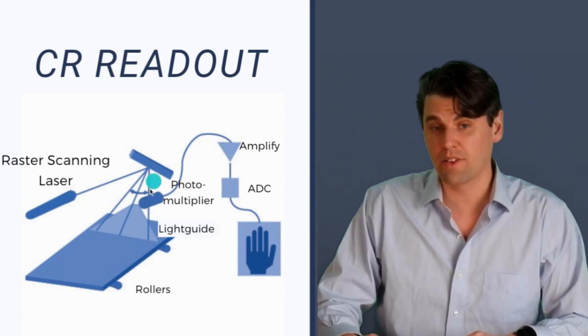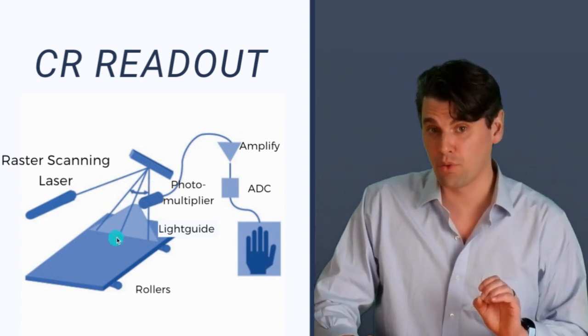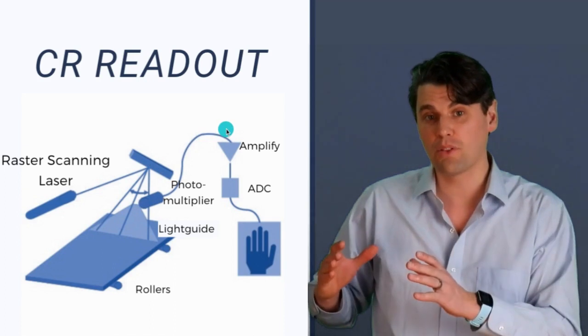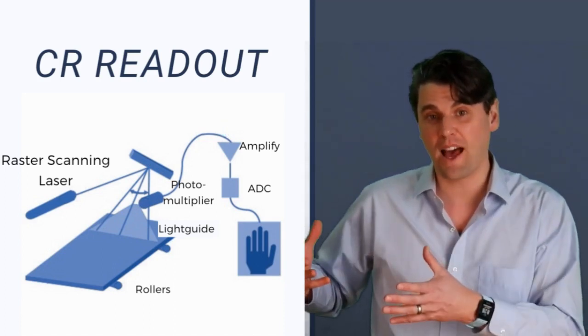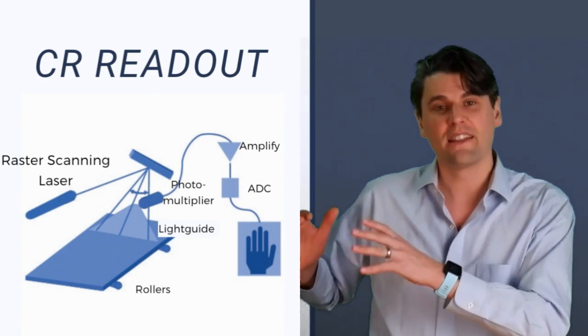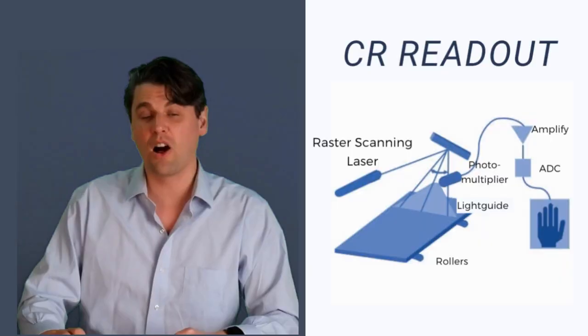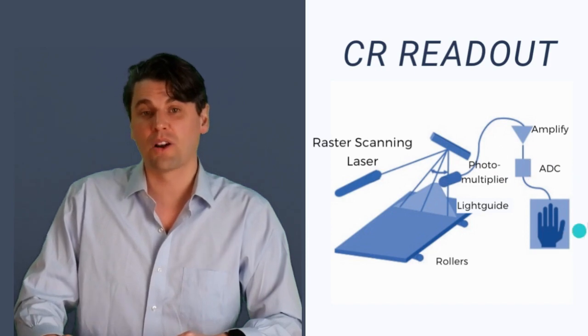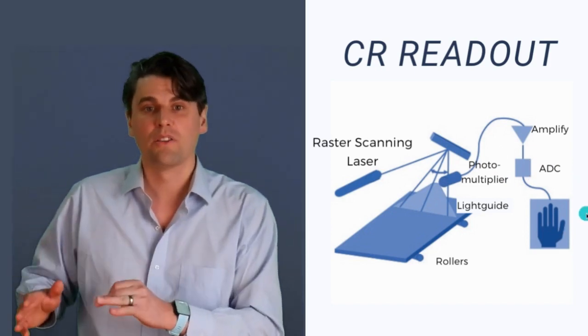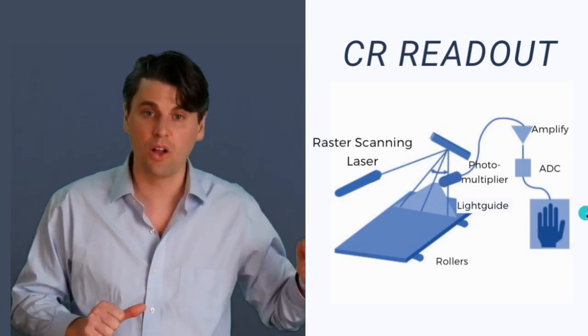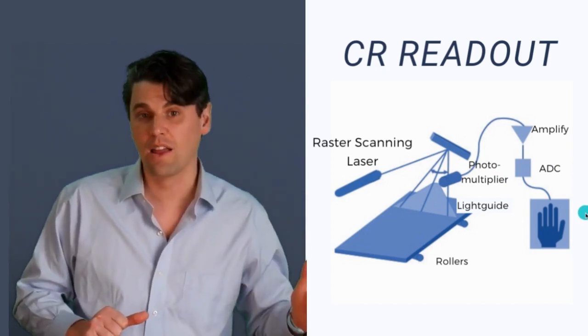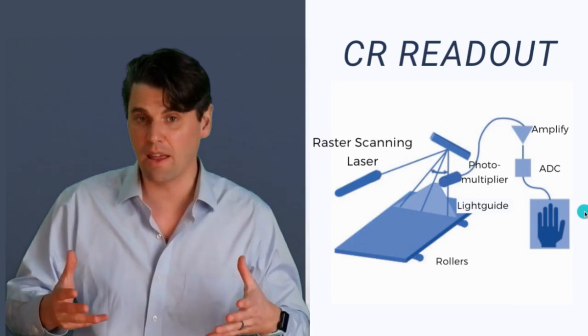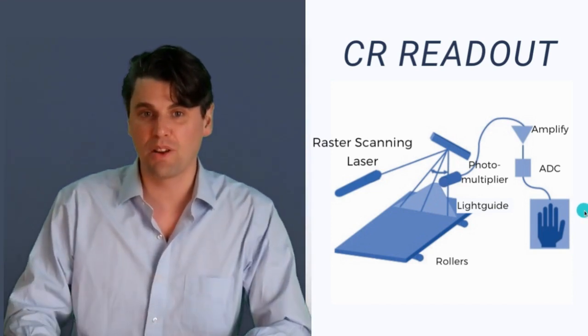That way we're going to fill up our whole image matrix one line at a time. The laser is going to free the light, that light is going to go through a light guide, then through a photomultiplier tube where the signal is amplified — it's still what's called an analog signal at that point. Then it's going to be digitized in a circuit we call an analog-to-digital converter, where we're essentially converting to a number. We start out with a latent image proportional to the exposure the panel saw, and what we get out is that number — and that's how we build up a digital image using computed radiography.